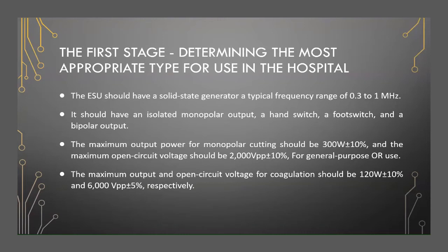The first stage, determining the most appropriate type for use in the hospital. The electrosurgical unit should have a solid-state generator, a typical frequency range of 0.3 to 1 megahertz, and it should have an isolated monopolar output and a hand switch and a foot switch and a bipolar output. The maximum output power for monopolar cutting should be 300 watts with a tolerance of 10%, and the maximum open circuit voltage should be 2 kilovolt peak to peak with a tolerance of 10%.